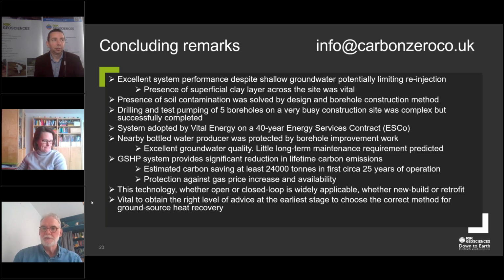So with any substantial closed loop system, you model the system knowing the properties of the plastic pipe and the properties of the surrounding geology to compute how many boreholes you're going to need. You then drill one or more test boreholes and thermally test that system to find out exactly how much heat can be sustainably extracted or injected. It's all part of the design process, whether there's transfer between one leg of the pipe and the other, that's calculated and modelled.